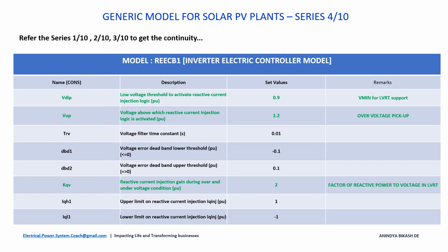In various grid codes, there are requirements of setting these KQV values. Also, this is a very critical parameter, and in practical scenario, what I have observed is that suppose that you have to maintain certain reactive power at the POC whenever there is any fault. So if you put KQV value equal to 0, there will not be any reactive current and no reactive power injected from the inverter during the fault condition. So when KQV is equal to 2, in that case, based on that settings, it will give certain reactive current and reactive power at the POC.